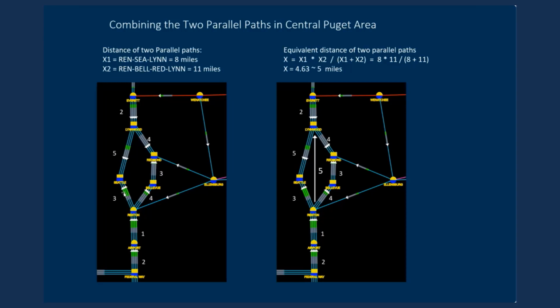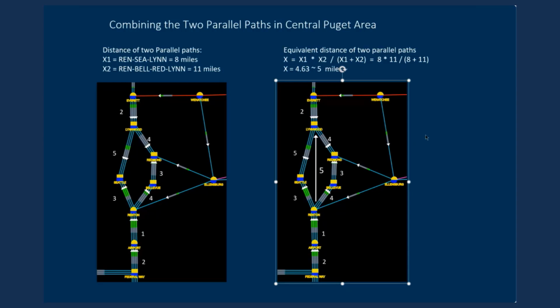First of all, we'll do the series combination of this path in series with this, and we get that the reactance from Renton to Seattle to Linwood is 8 miles, the 3 plus the 5. The second reactance from Renton to Bellevue to Redmond to Linwood is 11. The 4 plus the 3, which is 7, plus the 4, which is 11. Now we'll do our parallel combination. We've basically got a path of 8 around this way, 11 around this way, and the parallel path is the product of the two, the 8 times 11, divided by the summation, which is the 8 plus 11, and that comes to 4.63, or almost 5 miles.